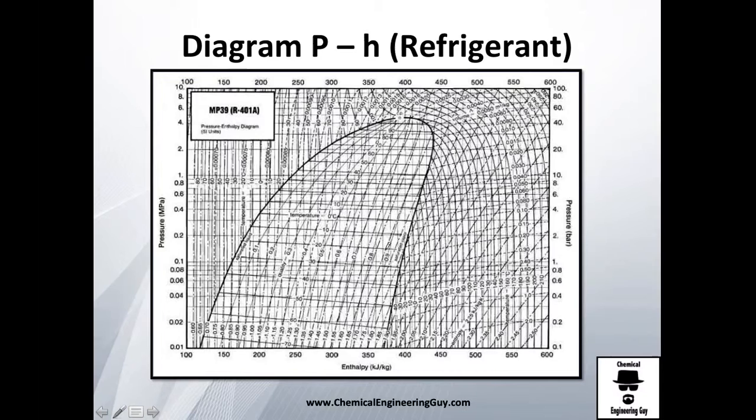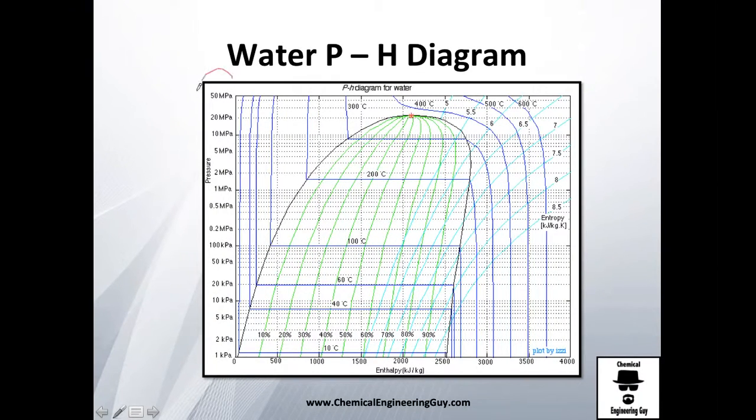Let's look at an actual diagram. R refers to refrigerant 401A—that's its specific name. You can see this line, the saturated line. This is liquid, this is gas, this is liquid plus vapor, and this is the critical point, which is marked. You have temperatures marked at 0, 10, 20, 30 Celsius. I'll explain how to read this later, but this is very useful. You have pressures and enthalpies.